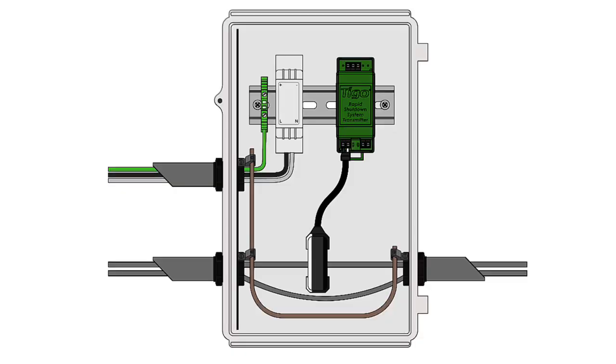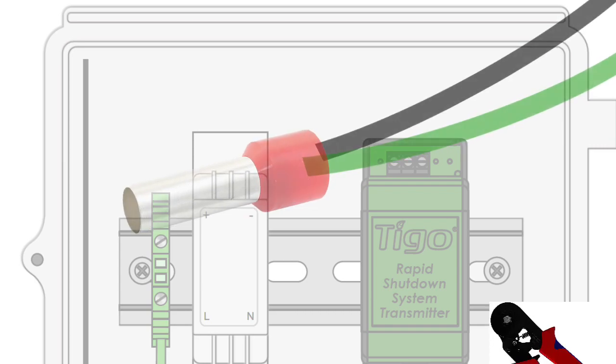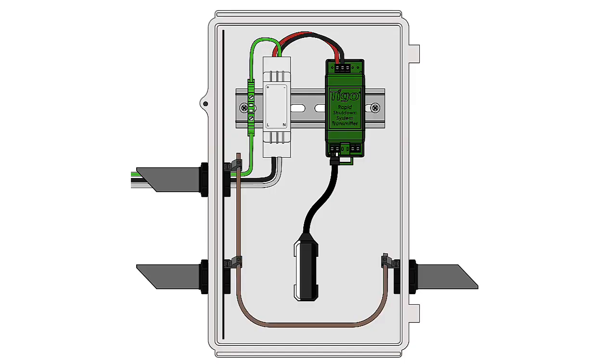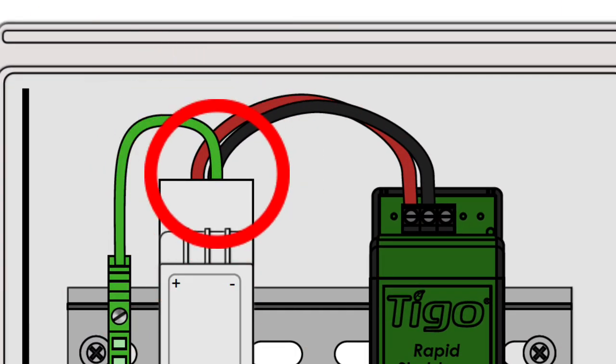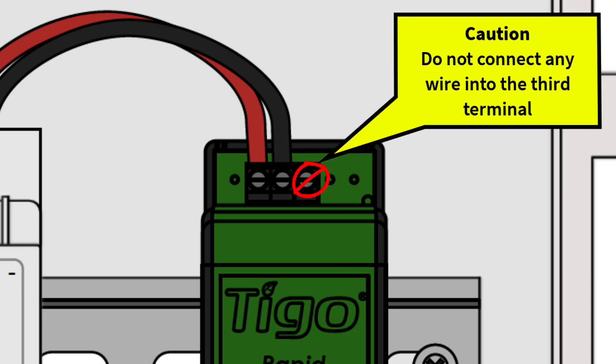Now let's switch gears to the top of the RSS transmitter and the three terminals you see here. Once the RSS transmitter, the power supply, and the grounding terminal have been mounted on the DIN rail, you must crimp one end of the red and black wires with a ferrule. The ferrulled end goes into the negative terminal of the power supply and the other end goes into the negative terminal of the RSS transmitter. The third terminal is not used.